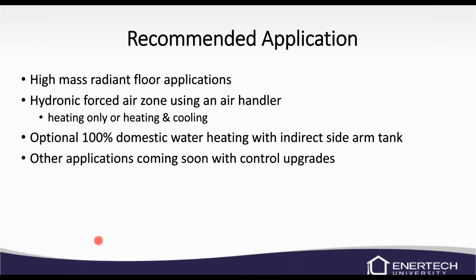So the recommended application for the WV unit is a high mass radiant floor application. So we've got good flow through there. The main thing on the WV unit that's so important is it's got to see minimum flow. So it's got to see at least, I think it's a little bit under 5 GPM. So if any zone can't handle 5 GPM, there's things we've got to do. Obviously, if every zone can handle 5 GPM and satisfy their heating load, then that would be the best way to go. So that would be a high mass radiant floor application.